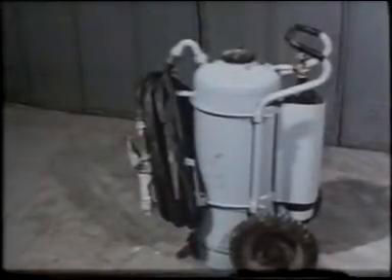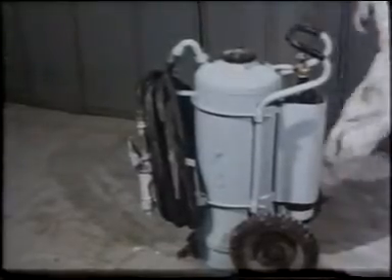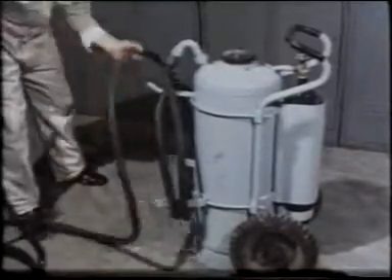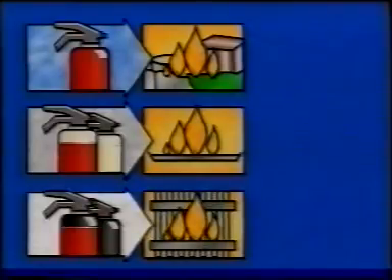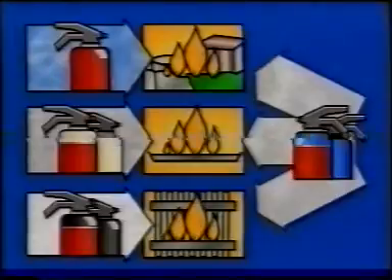There are also larger types of powder extinguishers, semi-portable, ranging from a 23 kilogram trolley for positioning by the manifold on a tanker up to a 67 kilogram wheeled unit for use in the engine room, for example. To recap, extinguishers color-coded red contain water for fires involving carbonaceous materials like furnishing, for instance. Cream-coded extinguishers contain foam for use with liquid fires. Black extinguishers contain CO2 for use on fires involving electricity. Blue-coded extinguishers contain powder for use with all types of fire dependent on powder type.